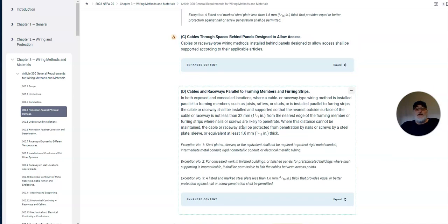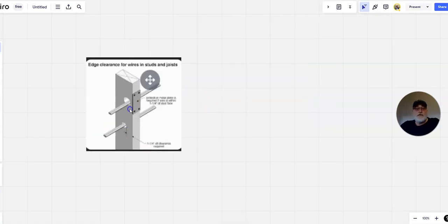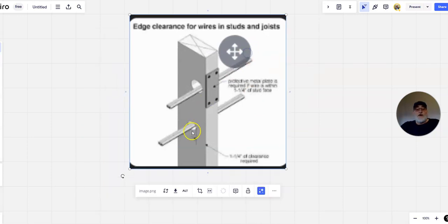And let's see, we're going to go on to cables and raceways parallel to framing members. In both concealed and exposed locations where cable and raceway type wiring methods are installed parallel to framing members, such as joists, rafters, studs, or installed parallel to furring strips, the cable or raceway shall be installed and supported so that the nearest outside surface of the raceway or cable is not less than 1.25 inches from the face of it. Again, we're going back to this right here, where we have 1.25 inches from wherever that penetration is, or the leading edge of that conduit. In this particular example, that's what they're talking about, the leading edge of where the sheetrock will actually be attached to the face of this and then screwed or nailed.